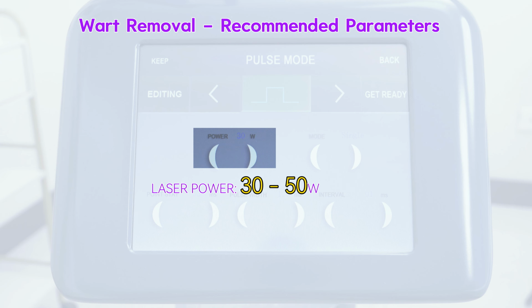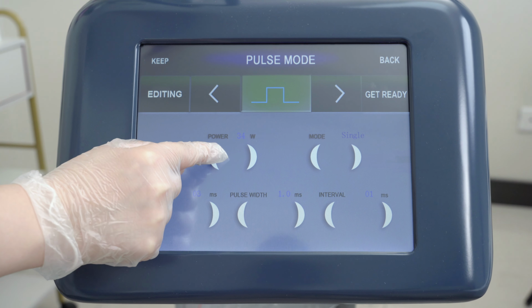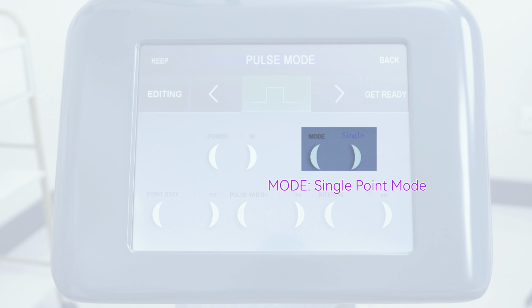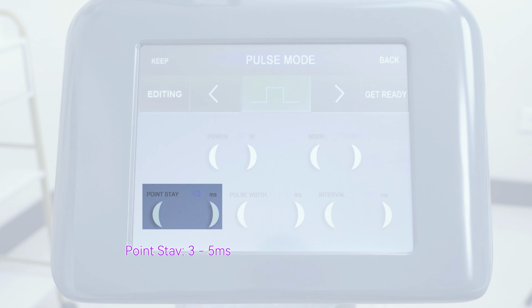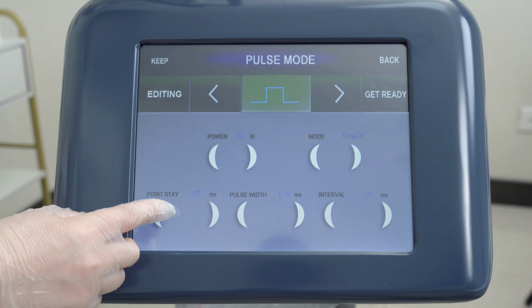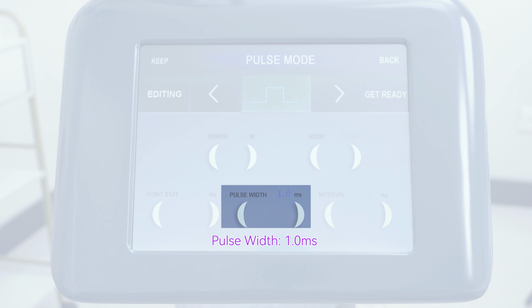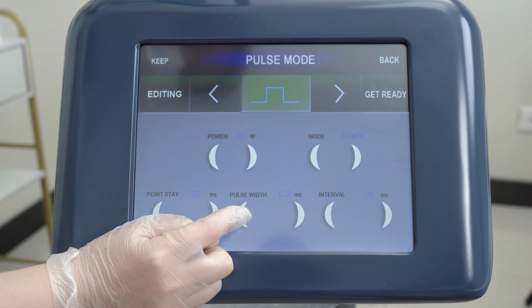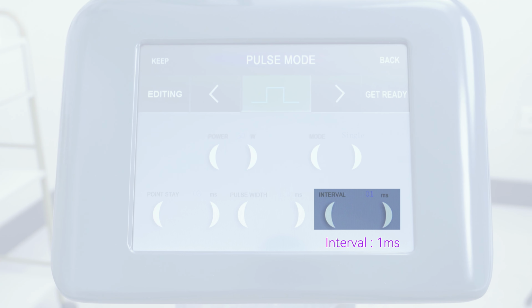Laser power, 30-50W. Mode, single point mode. Available modes: single point, continuous, pulse. Point stay, 3 to 5 milliseconds. Pulse width, 1 millisecond. Interval, 1 millisecond.